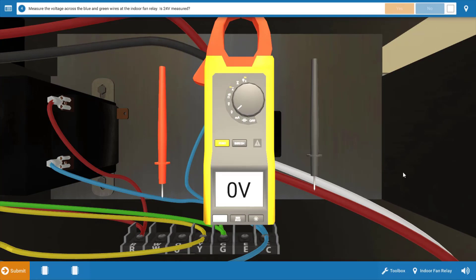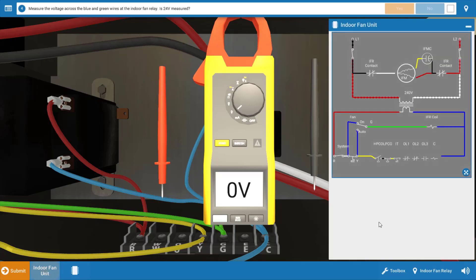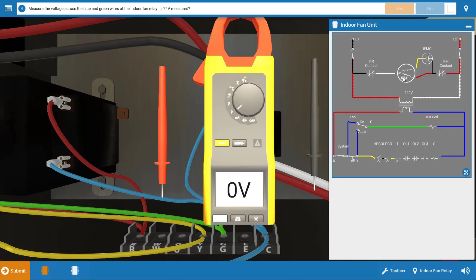Now before we take any voltage measurements, let's briefly review the wiring diagram by clicking on the bottom left here. And when we do that, we can see that the indoor fan is definitely one of our possible causes. We could have an open winding in the motor. It's also possible that the capacitor for the indoor fan is faulty.